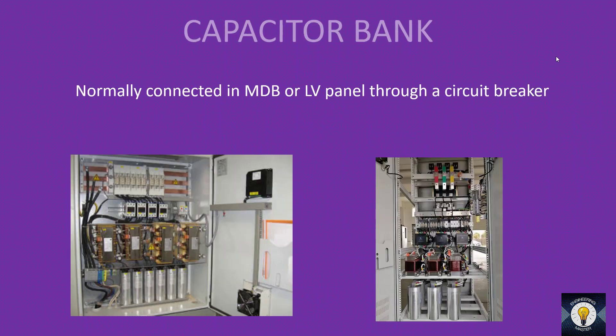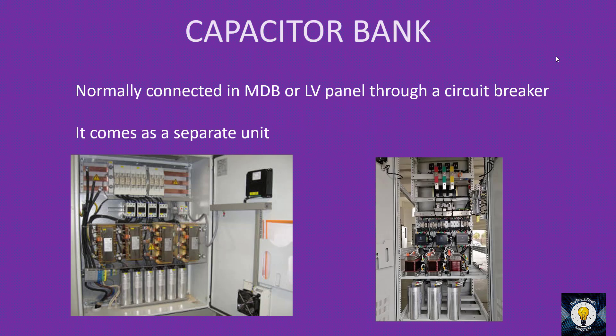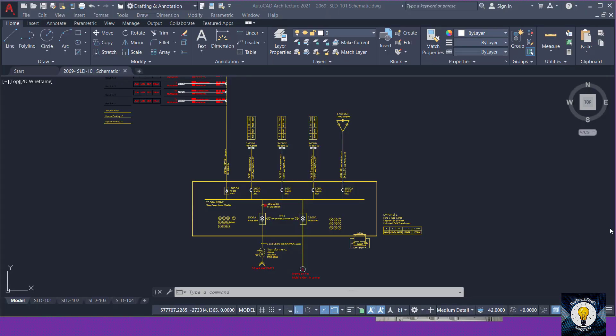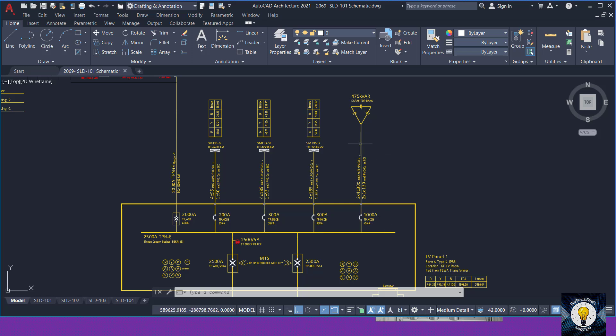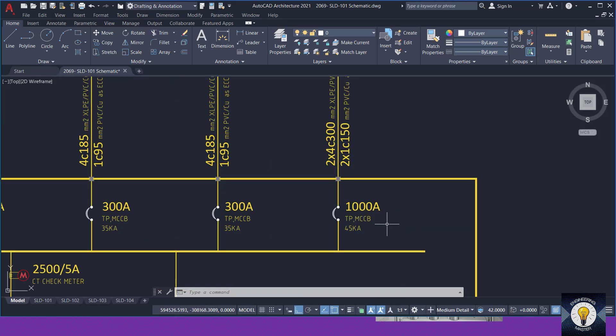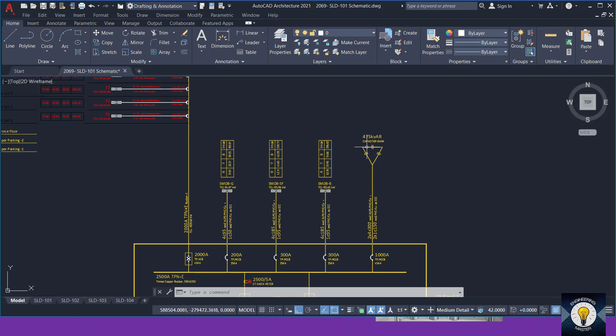Where is the capacitor bank installed? Normally on the LV side, it is connected to the main distribution board or LV panel through a circuit breaker, and it comes as a separate unit. This is the LV panel from one of my earlier projects. You can see the capacitor bank is connected to the LV panel through a 1000A TPMCCB and a cable, installed near the LV panel.